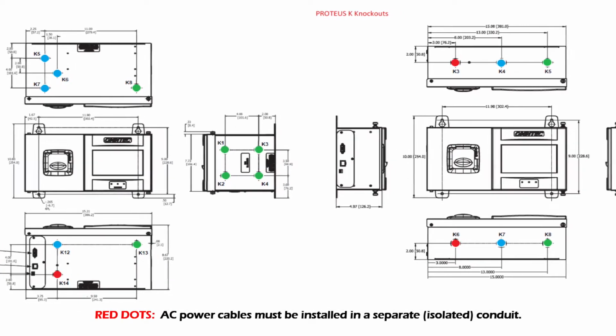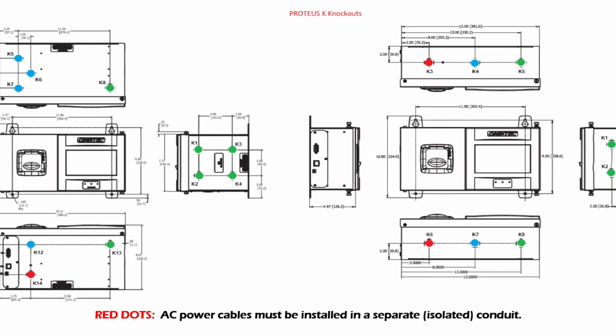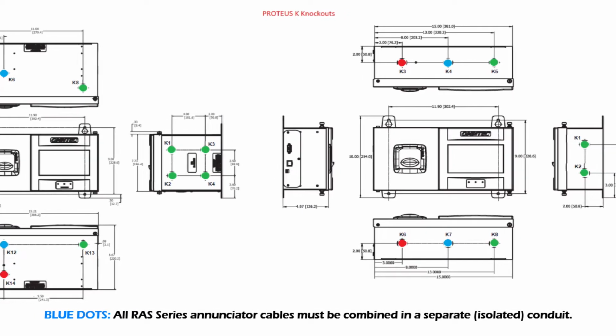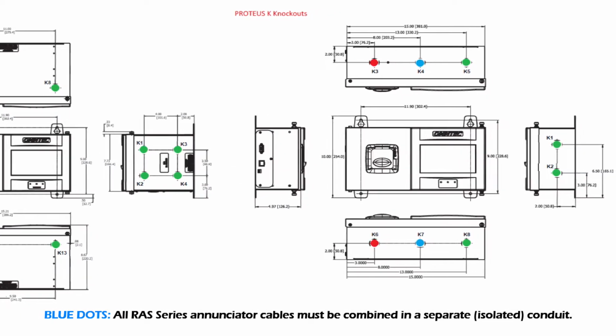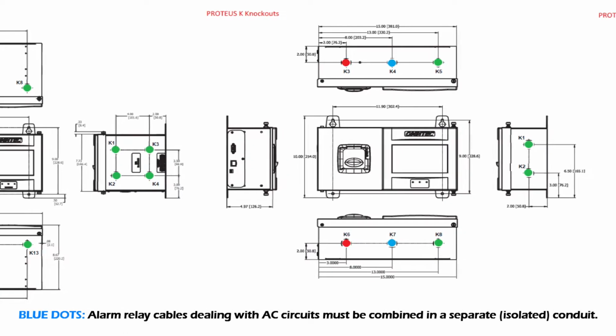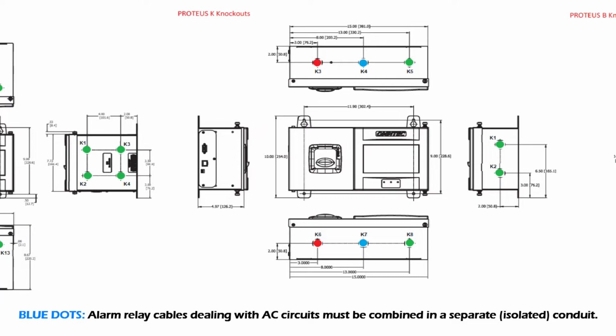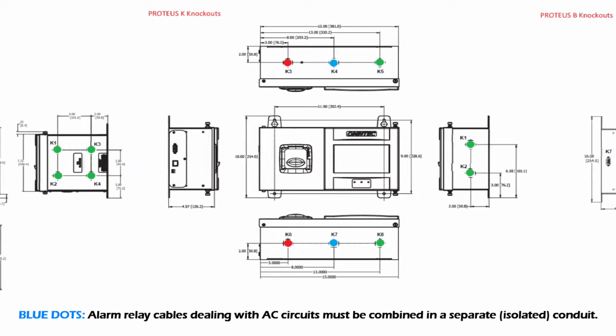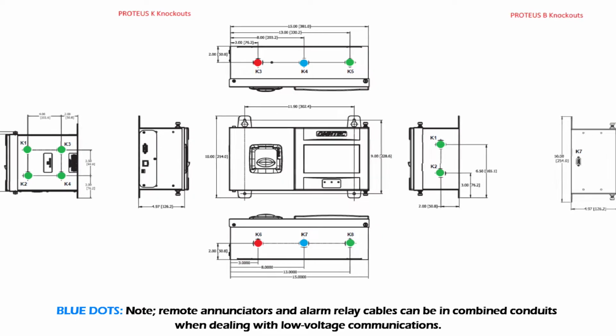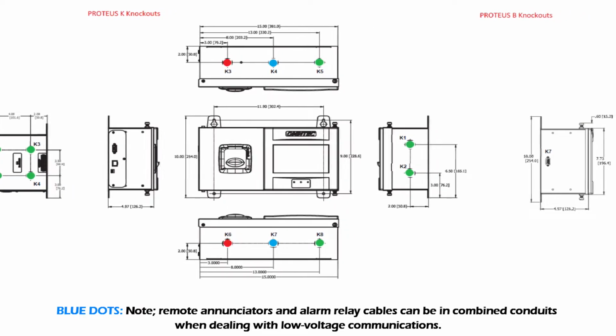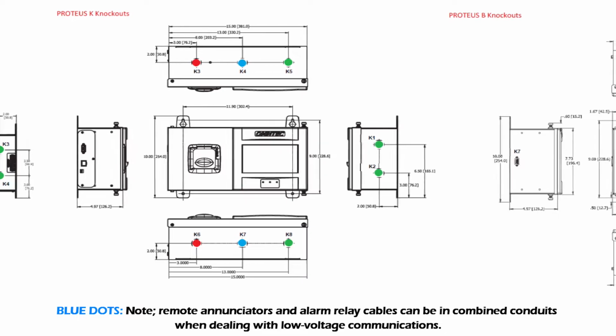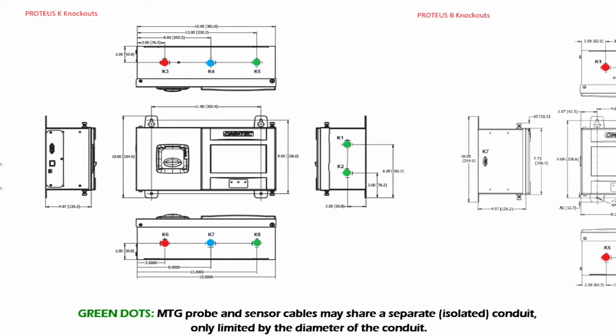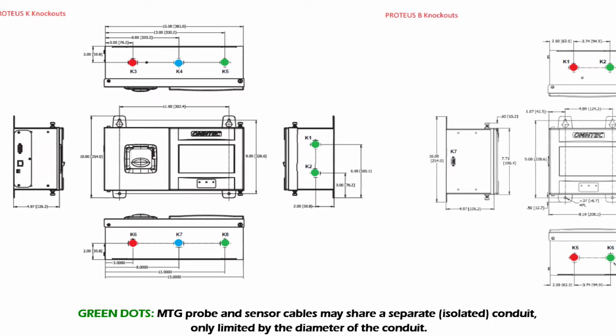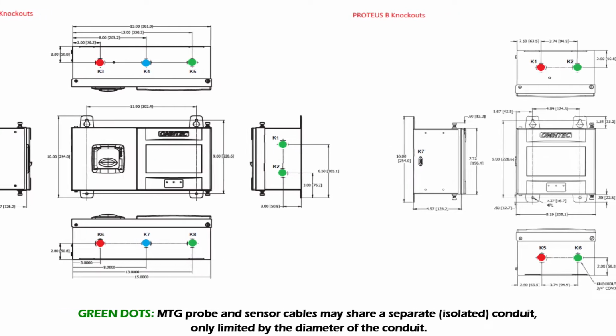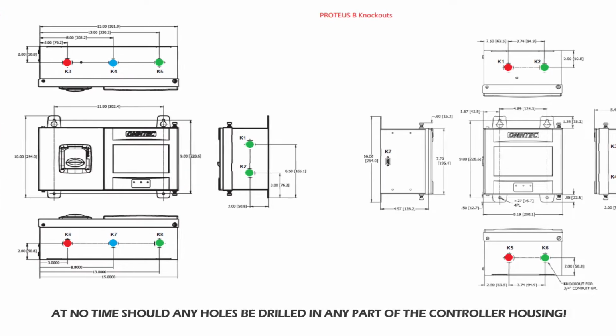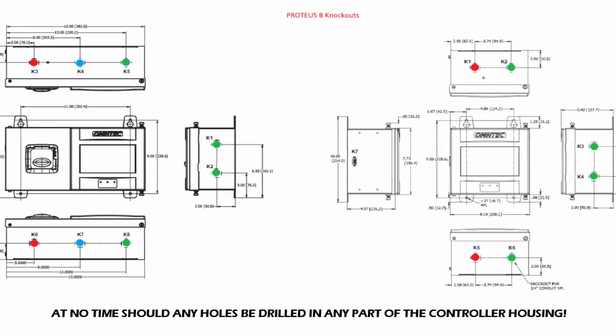AC power cables must be installed in a separate isolated conduit. All RAS series annunciator cables must be combined in a separate isolated conduit. Alarm relay cables, dealing with AC circuits, must be combined in a separate isolated conduit. Also note, remote annunciators and alarm relay cables can be in combined conduits when dealing with low voltage communications. MTG probe and sensor cables may share a separate isolated conduit, only limited by the diameter of the conduit. At no time should any holes be drilled in any part of the controller housing.